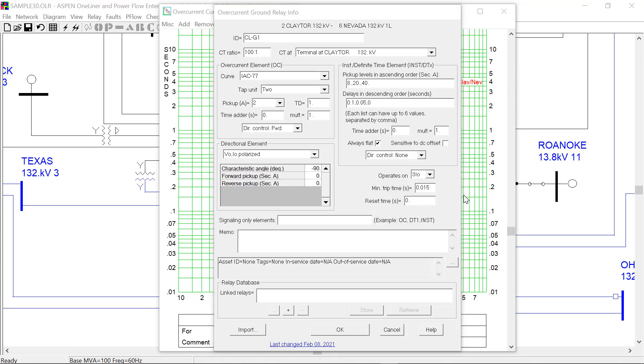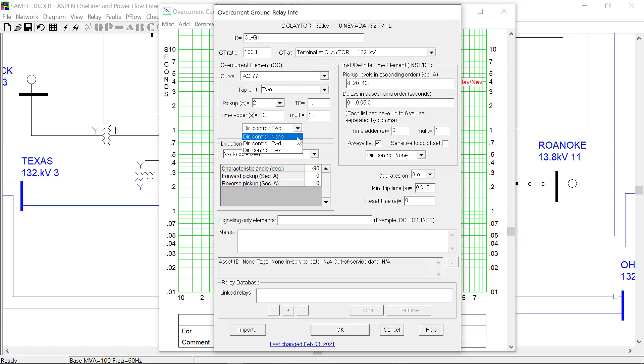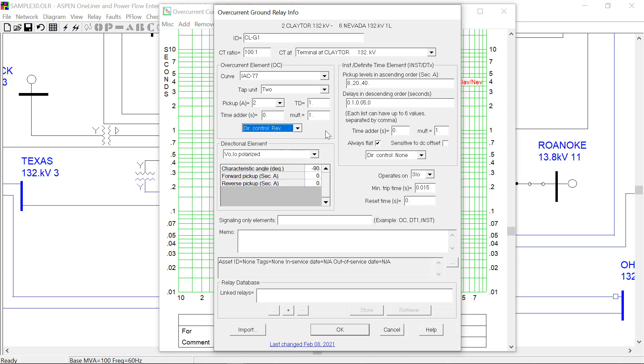The second set of new features is the directional control flag. In addition to none and forward like in the previous versions, now you can also specify the reverse direction for overcurrent element and also for definite time element.